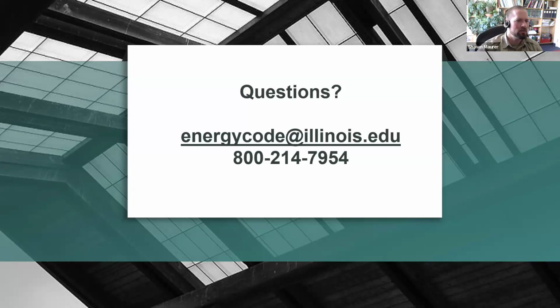Question here about pressure testing for institutional occupancy. Can the non-sleeping compartments have a separate test requirement? So yes, the sleeping and dwelling units have a specific sleeping and dwelling unit test that has to be done. The rest of the building would have to meet the sampling testing of the commercial building sampling procedure.